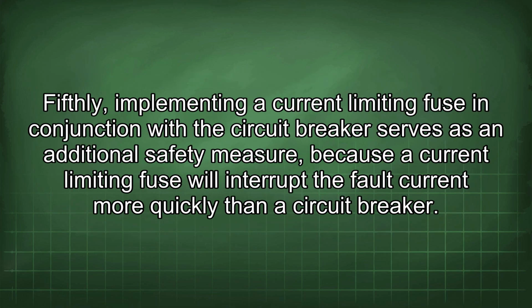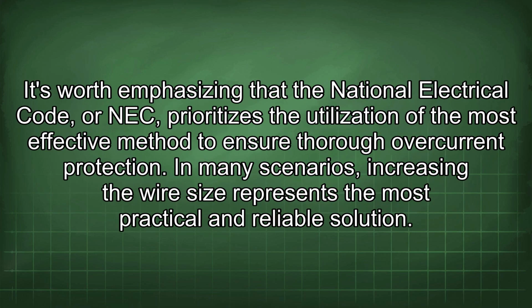Fifthly, implementing a current-limiting fuse in conjunction with the circuit breaker serves as an additional safety measure, because a current-limiting fuse will interrupt the fault current more quickly than a circuit breaker. It's worth emphasizing that the National Electrical Code, or NEC, prioritizes the utilization of the most effective method to ensure thorough overcurrent protection. In many scenarios, increasing the wire size represents the most practical and reliable solution.